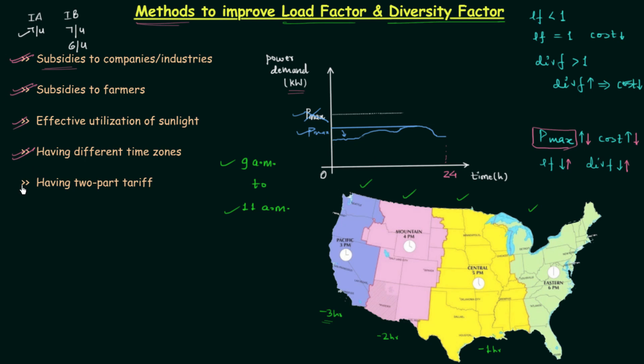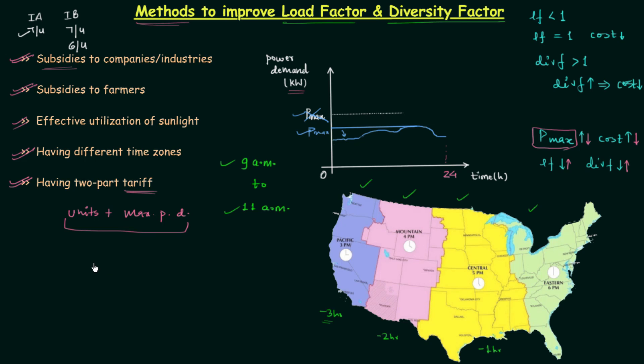The last method is having a two-part tariff. In this tariff, the first part is for the units the consumer is consuming and the second part is for the maximum power demand. So consumers are charged in two ways: for the units they consume and for their maximum power demand. There is also a tariff based on power factor — we provide subsidies to industries which use high power factor loads. We will discuss this in detail when we cover power factor. These are the different methods by which we can improve the load factor and diversity factor.